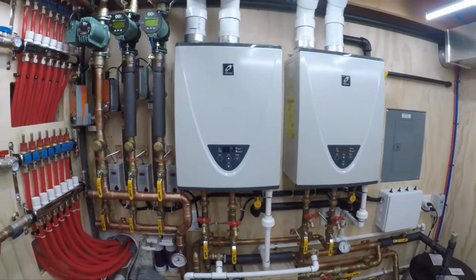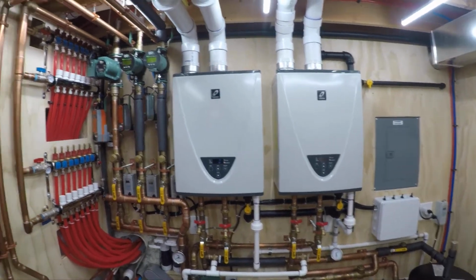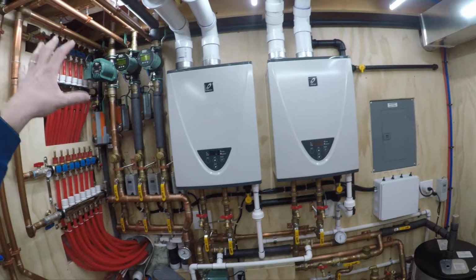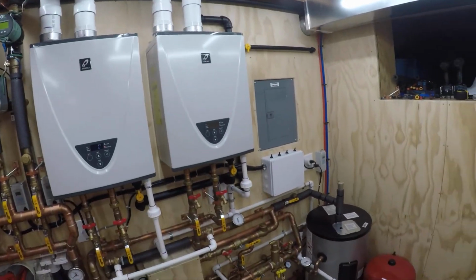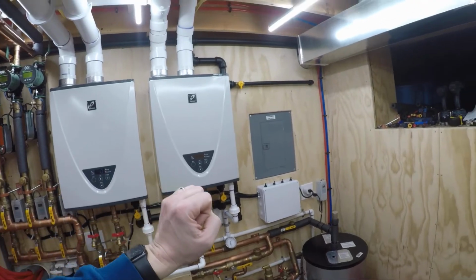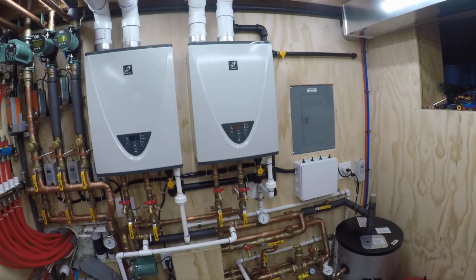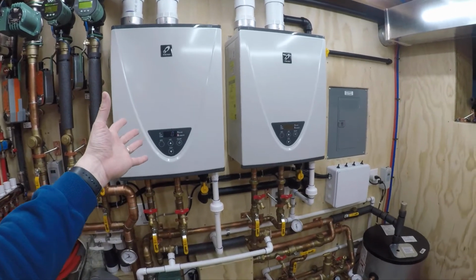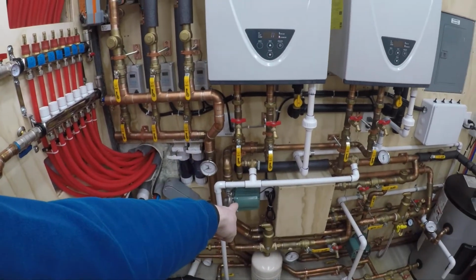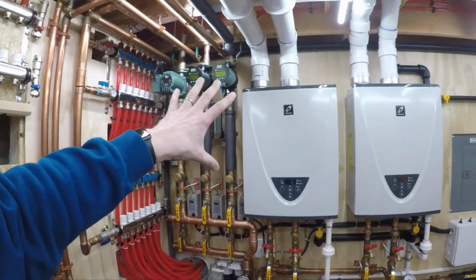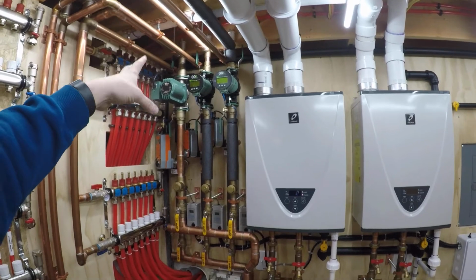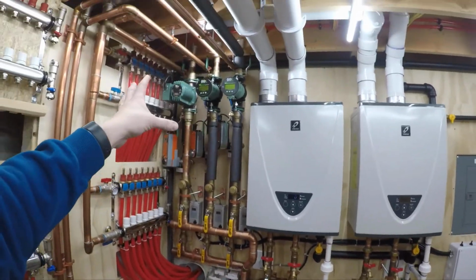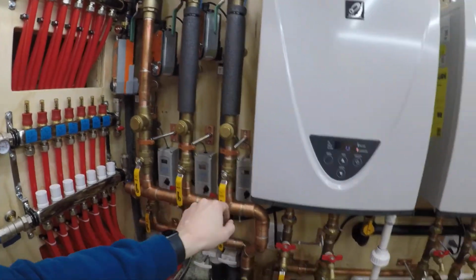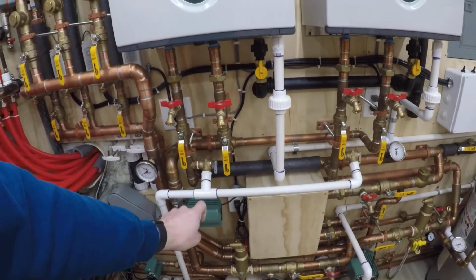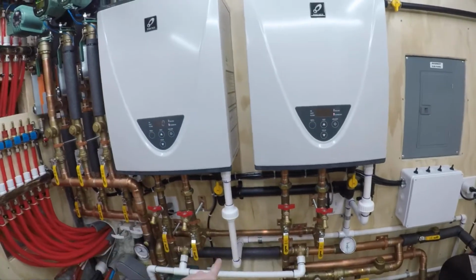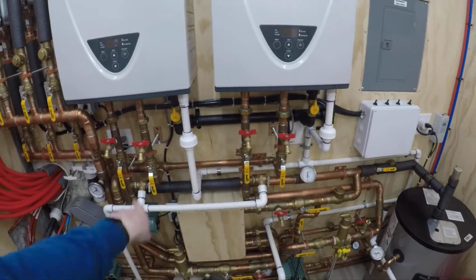Okay, now let's say there's a call for heat or snow melt. All right, because these fluids don't touch, the glycol's on one side of the flat plate. The domestic hot water's on the other side of the flat plate. You need something to turn on the heaters in order to produce the heat. That's where this pump comes in. So whenever there's a call for whether it be radiant heat, snowmelt heat, slab, garage, basement, whatever, these aquastats have the ability to turn on this pump.